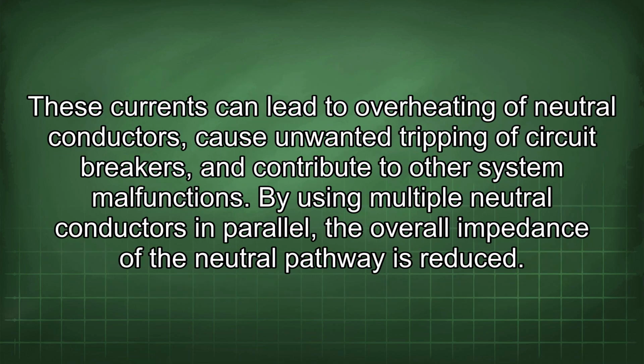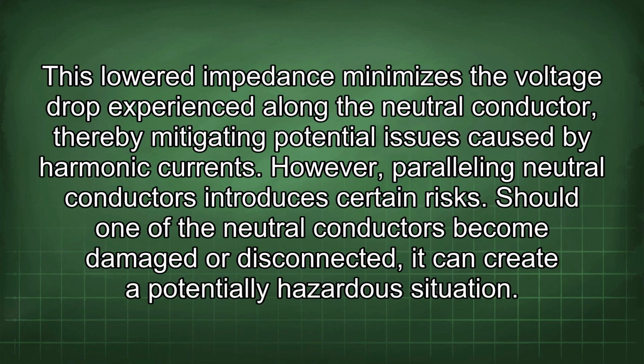These currents can lead to overheating of neutral conductors, cause unwanted tripping of circuit breakers, and contribute to other system malfunctions. By using multiple neutral conductors in parallel, the overall impedance of the neutral pathway is reduced. This lowered impedance minimizes the voltage drop experienced along the neutral conductor, thereby mitigating potential issues caused by harmonic currents.